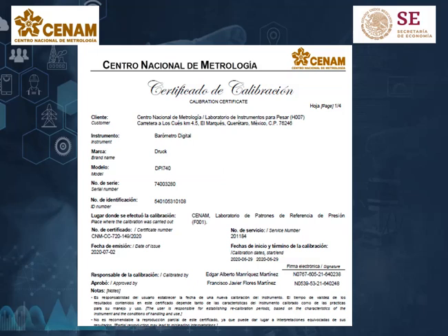This is an example of a cover. As we can see, we have the customer information, item or items information, place of calibration, the unique identifier, the service number, the date of issue, and the begin and end dates, the names of responsibles with the electronic signature. At the end, we add some general statements.